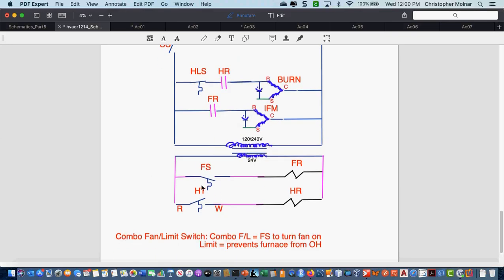Now, what temperature do I want this to come on? What temperature, roughly, do I want this whole blower motor to start? 200. What's your body temperature? 200 is where I shut the high limit off. Okay, 200 I open my high limit. But where do I want the blower to start? 96, 98. Since we're not going to tie it in that tight, how about 100? That works. Okay. I want it to start over your body temperature.